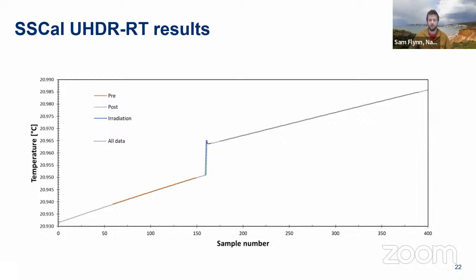And all we need to do with this result is just extrapolate to the midpoint and calculate the radiation-induced temperature rise. An interesting feature of this one is that because the thermistor is directly being irradiated, the temperature after the flash irradiations is slightly higher than the graphite around it, and you can see that as a small decay. That's not a problem, it's built into this calibration factor.